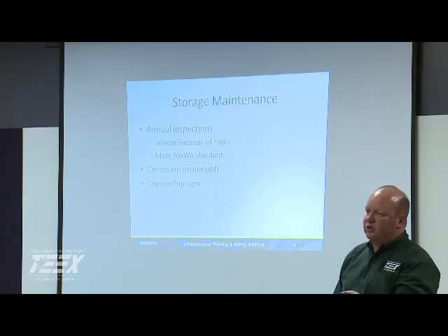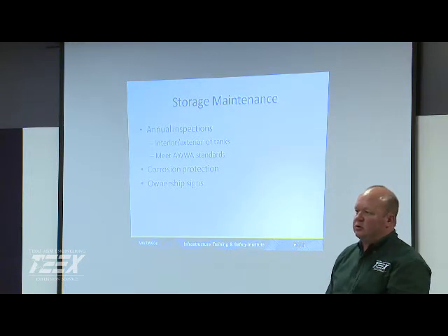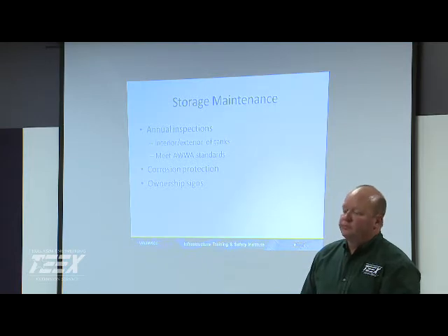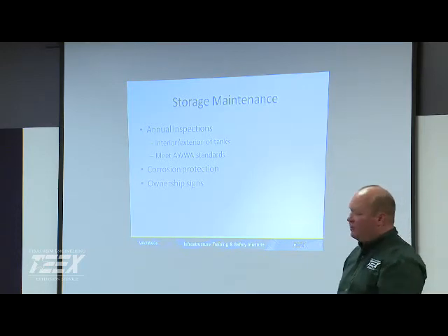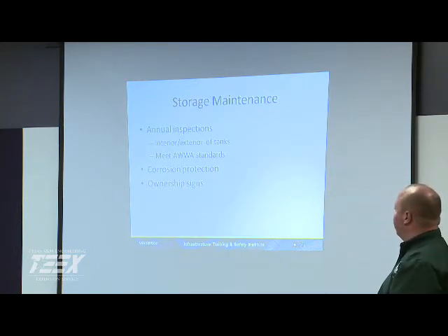Yeah. You'll have consultants that come in and do inspections. They look at wall thickness. The water systems will go out and hire a tank inspection company that can do the tank inspections. So we really don't have a set time frame for the painting unless it's peeling off in chunks. Well, that's a lot of it. You've got to be able to measure somehow, so you've got a consultant group coming in. And there's a lot of different factors that'll affect your coating life.